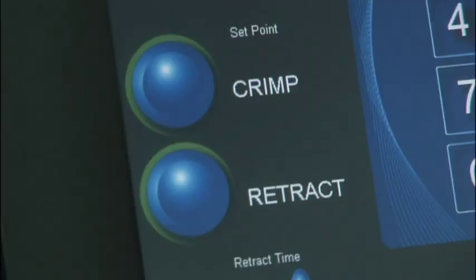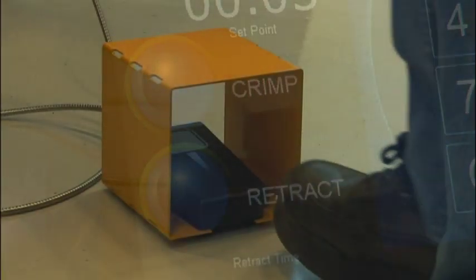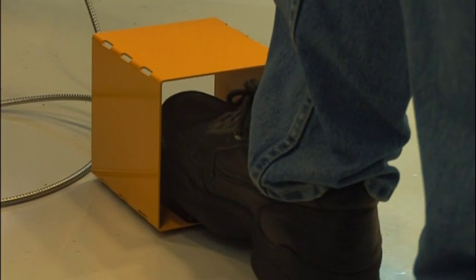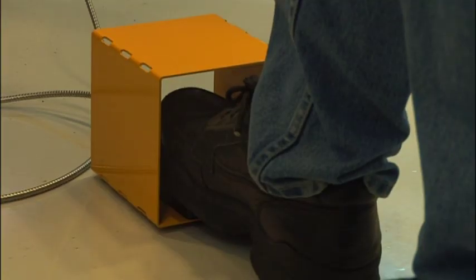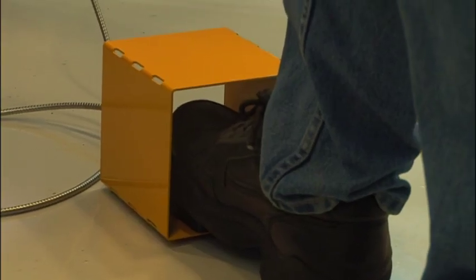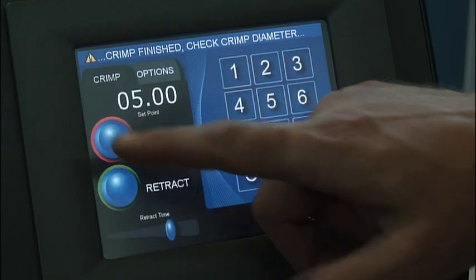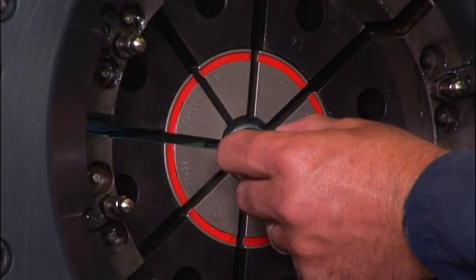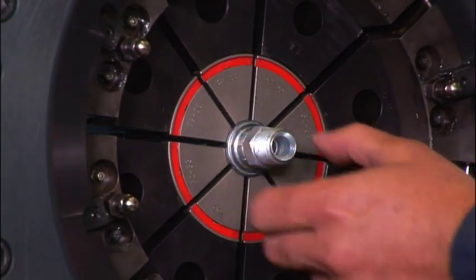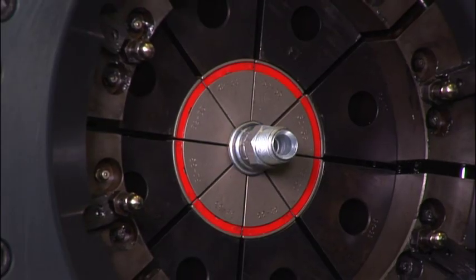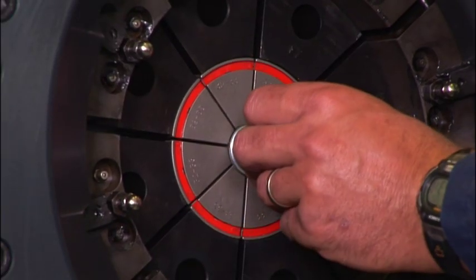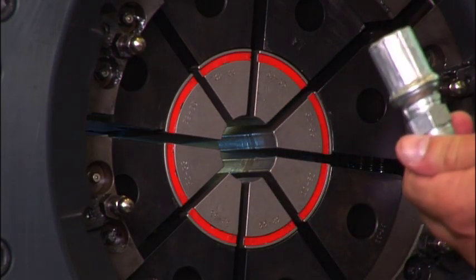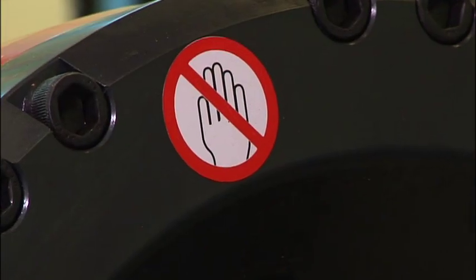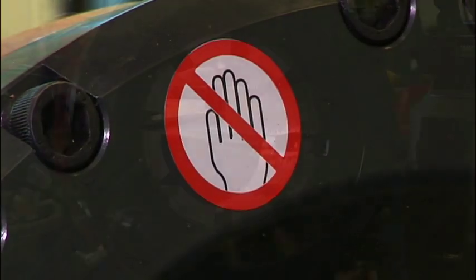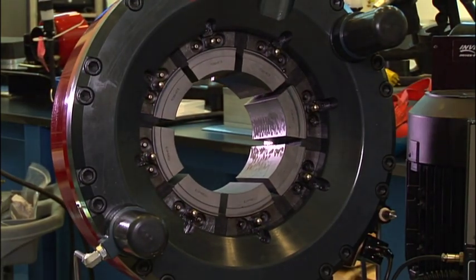The crimp button, the retract button, and the foot pedal on the GC96 operate on a dead man control. They only operate as long as you depress the buttons or hold the foot pedal down. The crimper stops immediately if the switch is released. To prevent serious injury, keep away from all moving parts. If bodily contact should occur with a moving part, immediately release the crimp button or foot pedal. Do not operate the crimper with hands, fingers, or any body part in the crimper mouth. Serious injury can occur. Keep additional personnel away from the crimper while operating.